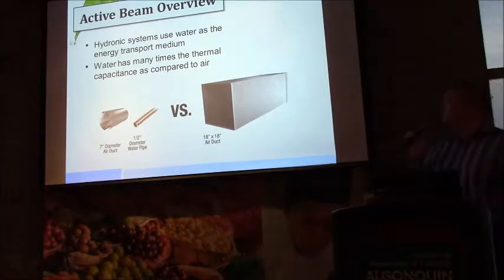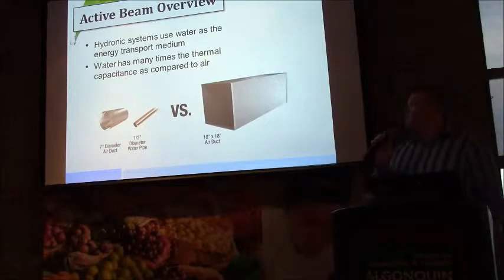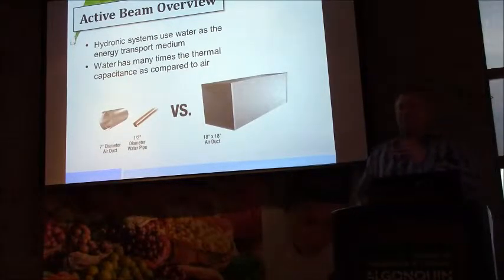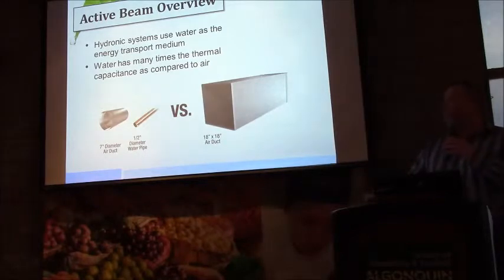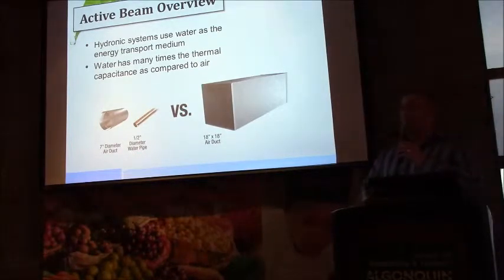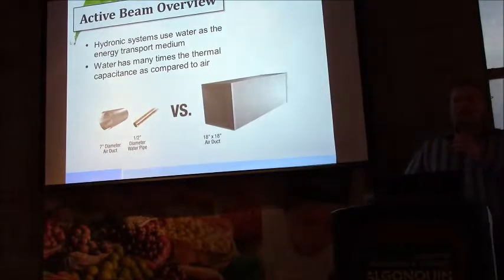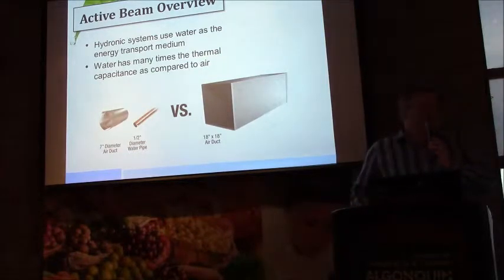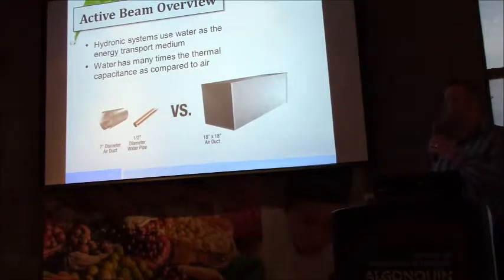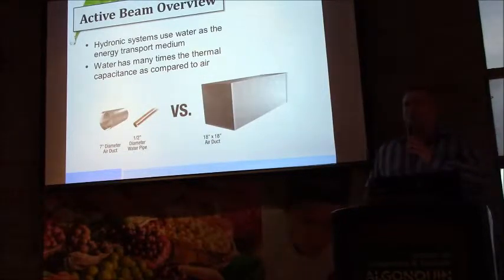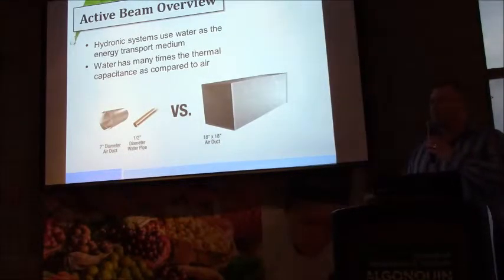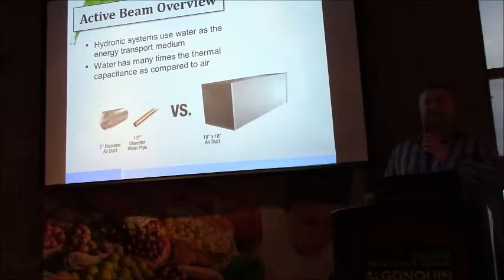But the effective philosophy or the strategy of a decoupled ventilation system is to replace the capacity that would be delivered in an all-air system, and in this case it's depicted with an 18 by 18 inch air duct, with a primary air duct sized for the minimum ventilation or the minimum primary air, in this case a 7 inch diameter round duct, and a 1/2 inch water line. Given that water has 3,400 times the heat-carrying capacity of air, the goal in this strategy of the decoupled ventilation is fundamentally to reduce the total air consumed at the primary air handling unit, which translates into direct energy savings.